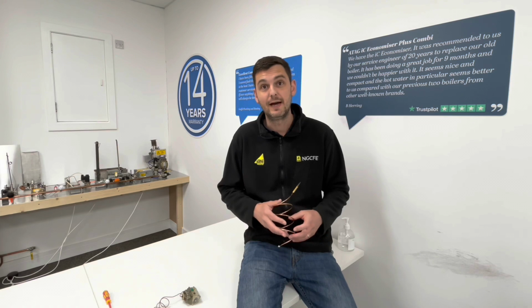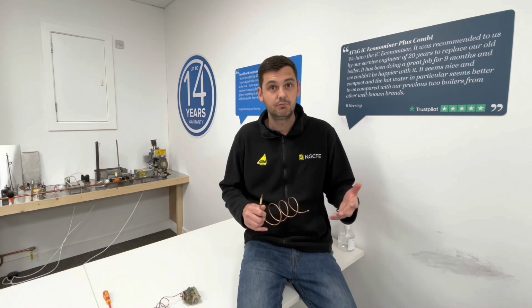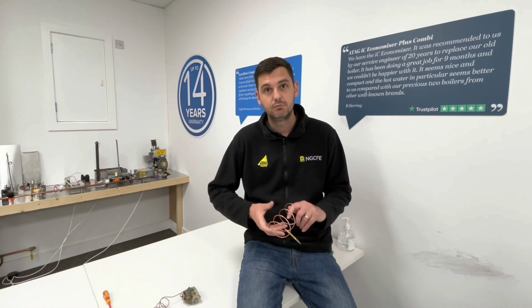After that, most appliances that we're concerned with are 60 seconds, apart from water heaters between 35 kilowatts and 70 kilowatts that are 45 seconds. And again, it's important to check manufacturer instructions because some manufacturers might specify different allowances for their appliances, in which case you go with the MIs. So how are most flame supervision devices going to work? A lot of them use thermocouples and thermoelectric valves.